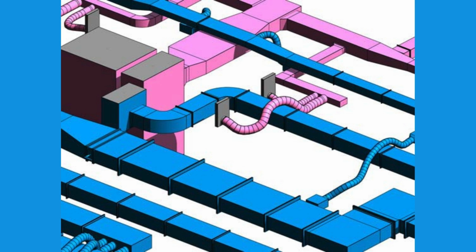Using smooth duct materials. Galvanized steel is a common choice due to its durability, but fiberglass and lined ducts offer lower friction. Minimizing fittings, bends, elbows, and transitions in the ductwork, as they create turbulence and pressure drops. Using smooth, long radius elbows instead of sharp turns can significantly reduce these losses.